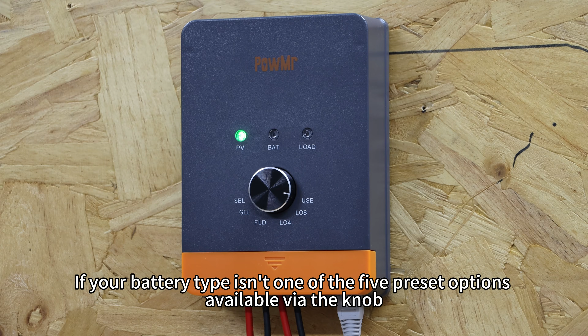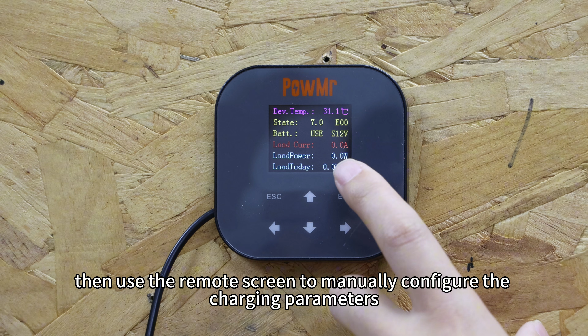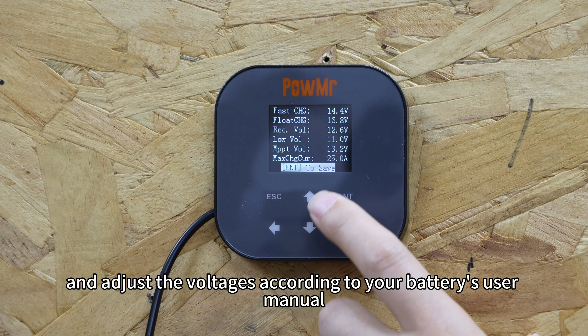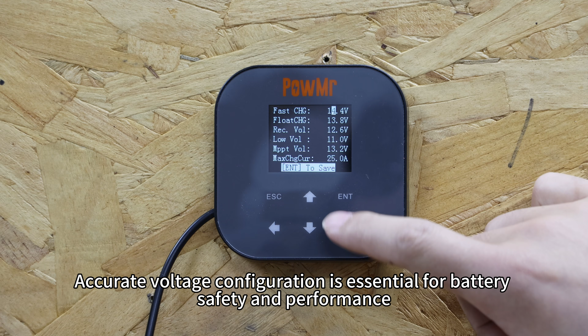If your battery type isn't one of the 5 preset options available via the knob, select USE mode. Then use the remote screen to manually configure the charging parameters. Enter the menu, go to the charging parameter settings, and adjust the voltage according to your battery's user manual. Accurate voltage configuration is essential for battery safety and performance.